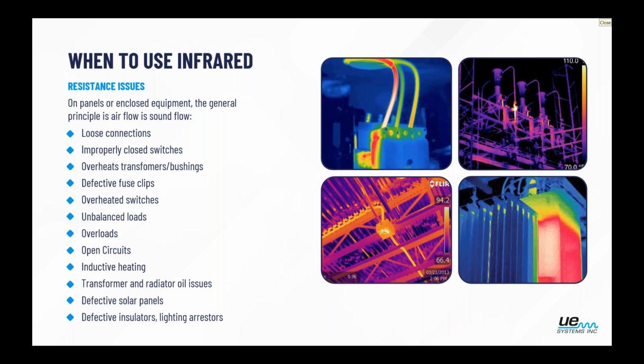And then another one where I would like to use both technologies at the same time, going back to the transformers. While we're listening for the bushing and the camera, the infrared camera is also looking for overheat on the transformer, we could also see if there's an issue with the radiator, if the oil level is not where it should be, if it's unusually hot or cold in certain spots where it shouldn't be.